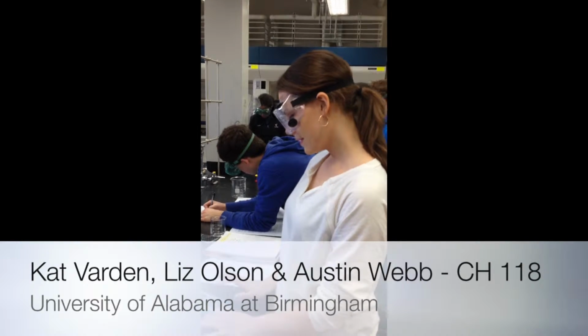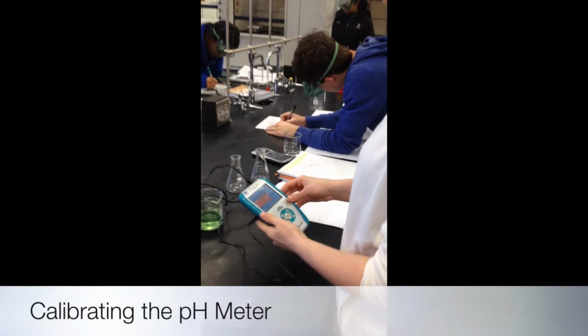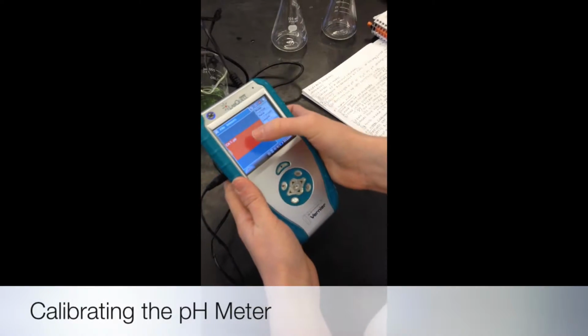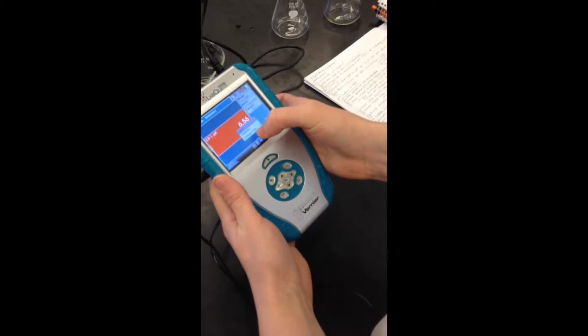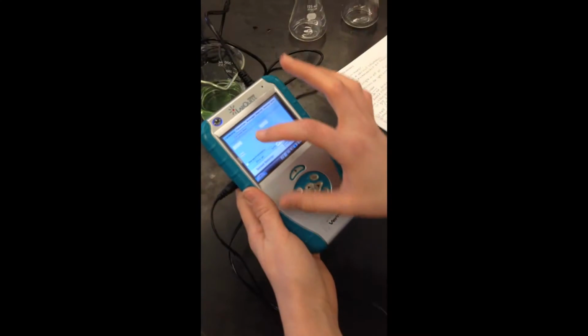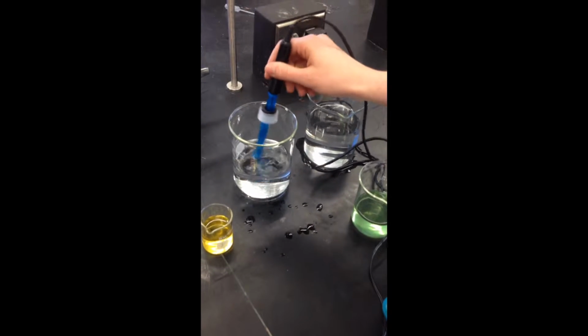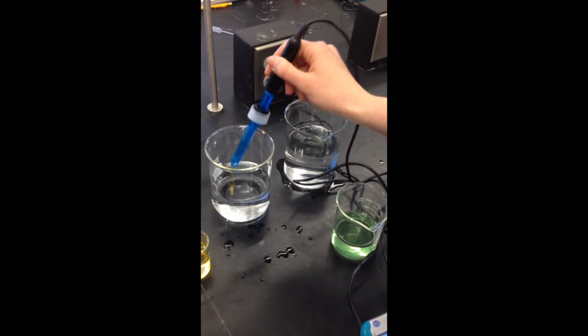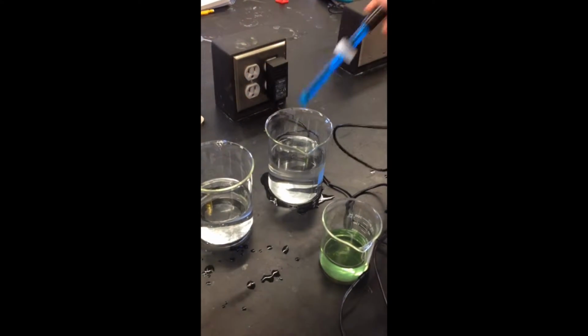Okay, I'm about to calibrate the pH meter, so I'm going to start by hitting the red box. And then I'm going to hit calibrate, and then I'm going to hit calibrate now. I'm going to go ahead and put in pH 4, and I'm just taking it out of the storage solution, and then I'm going to rinse it in water.